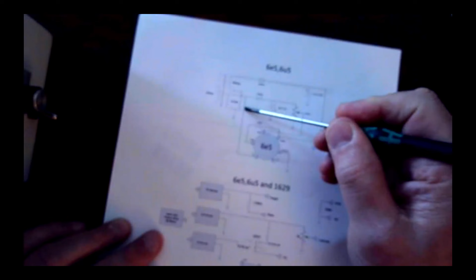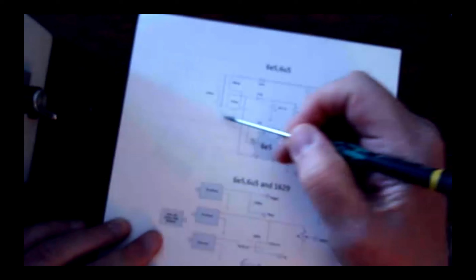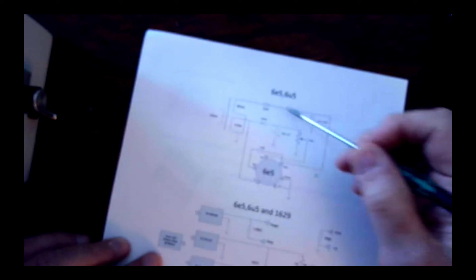Now, if you try to use these modules with a common ground between the modules, these units - because this is all AC driven side of the transformer, and on the other side here is my DC side, the positive and the negative - you can't do these with the modules. They don't like it, they don't. They will fight each other.